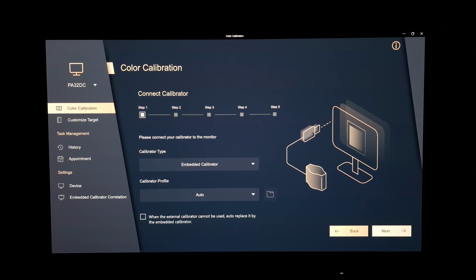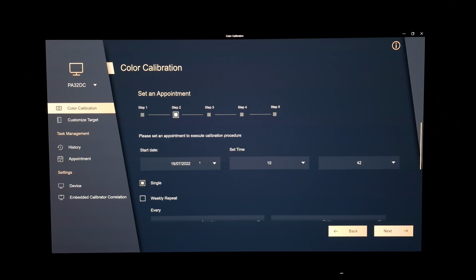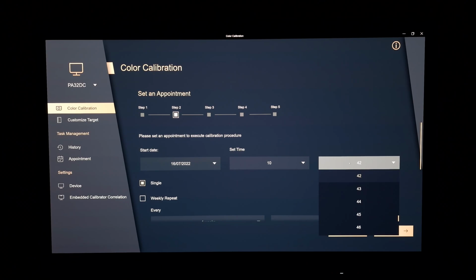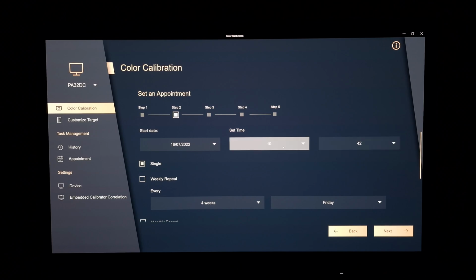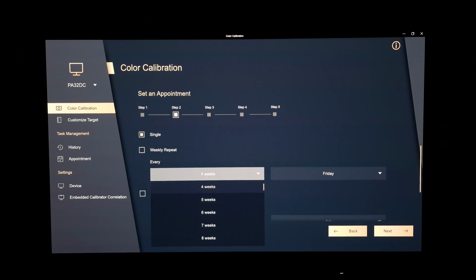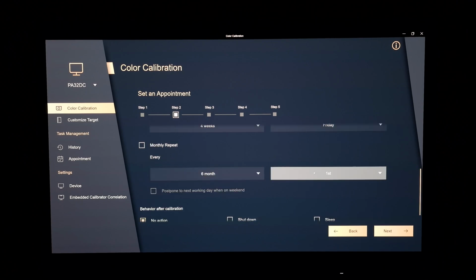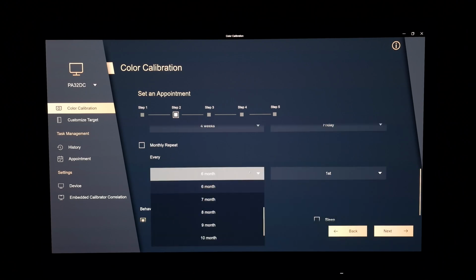You then press next. So remember, I'm setting an appointment here, so you can have a schedule. You can have it at a start date of, this is several minutes from now, basically. That's when it's going to be doing it, if you want just a single calibration. If I knew I wasn't going to be using my screen, say at 4 o'clock today, and I wanted it to just do its thing, calibrate it for me without me being there, then you can do that. You can have weekly repeats set, so you can have it set to calibrate every week, 2 weeks, etc., up to 52 weeks on a given day. And you can do the same monthly as well, on a specific day of the month, once every 1 month, 6 months, 12 months, whatever it is.